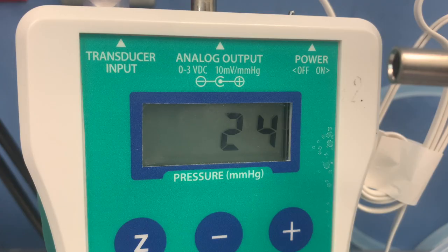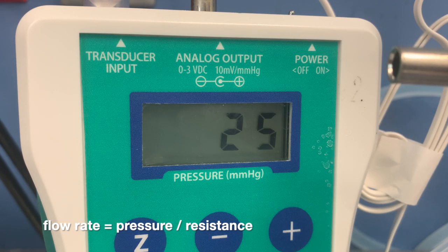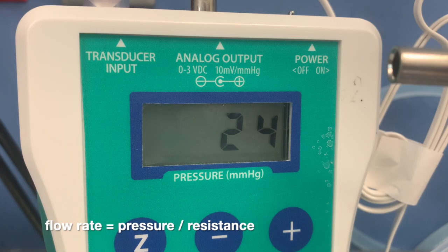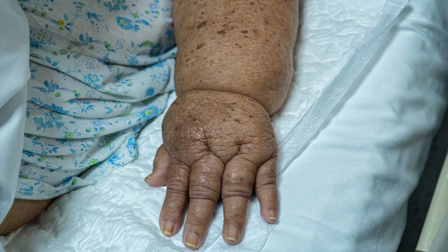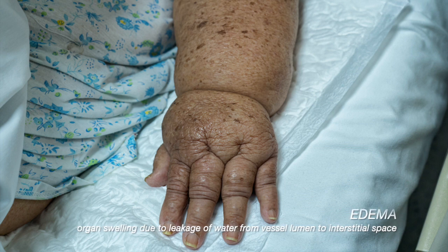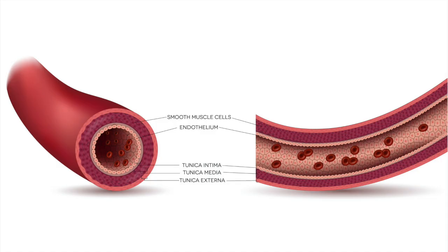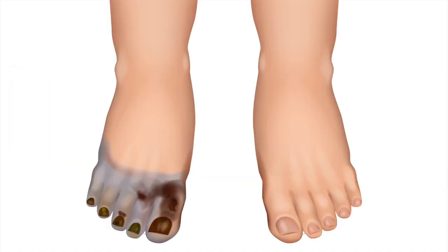The pressure experienced within the organ is one of the most important measurements and in most cases determines the flow rate, as pressure and flow are directly related. Pressure corresponds to resistance experienced within the blood vessels. Too high pressure can cause fluid to leak into the tissue, also known as edema, or it can cause endothelial damage. Too low pressure can lead to insufficient perfusion at the edges of the organ.